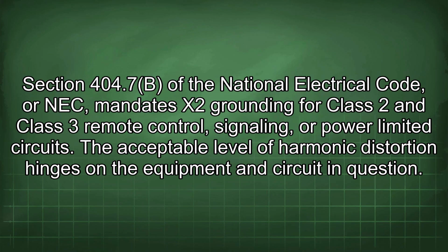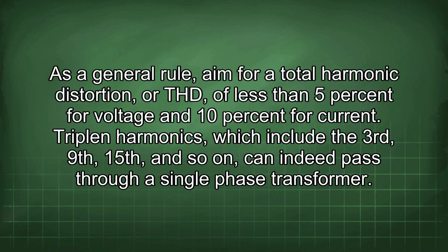Section 404.7b of the National Electrical Code, or NEC, mandates X2 grounding for Class 2 and Class 3 remote control, signaling, or power-limited circuits. The acceptable level of harmonic distortion hinges on the equipment and circuit in question. As a general rule, aim for a total harmonic distortion, or THD, of less than 5% for voltage and 10% for current. Triplen harmonics, which include the 3rd, 9th, 15th, and so on, can indeed pass through a single-phase transformer.